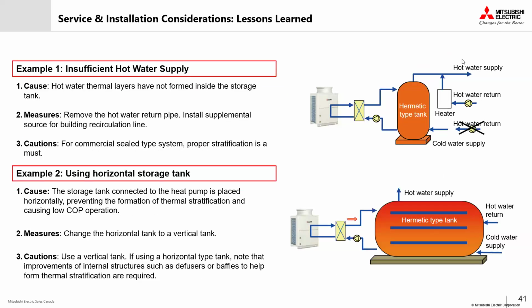So lastly here, we'll just look at some of the lessons learned that we've acquired over the years from the field. Every project teaches us something different, whether from successes or from challenges. One of the common issues we've seen for a lot of these CO2 heat pump water heating systems is insufficient hot water supply out into our building, which often traces back to poor stratification in the storage tanks.